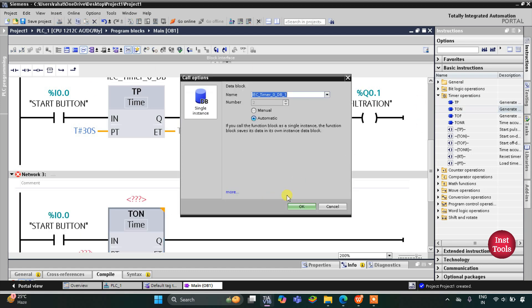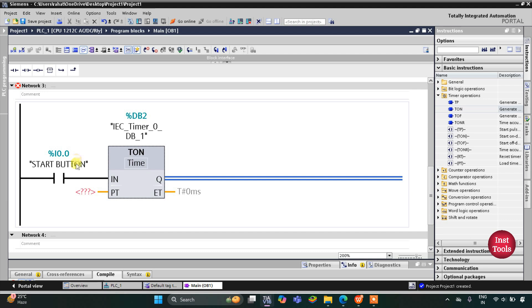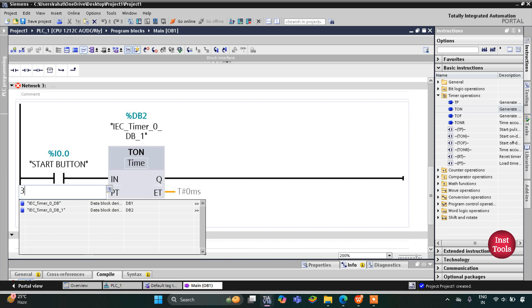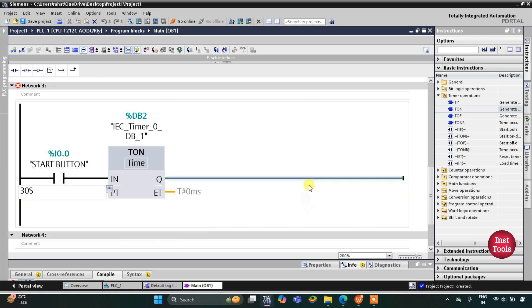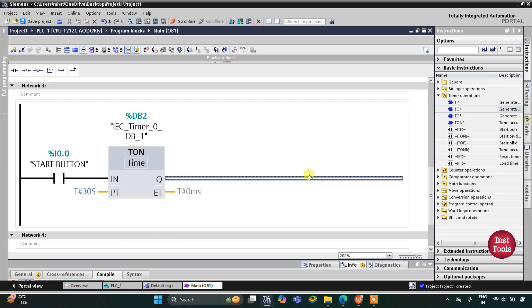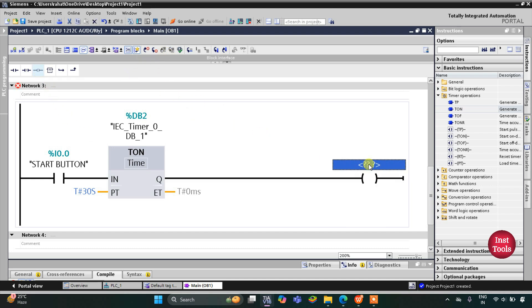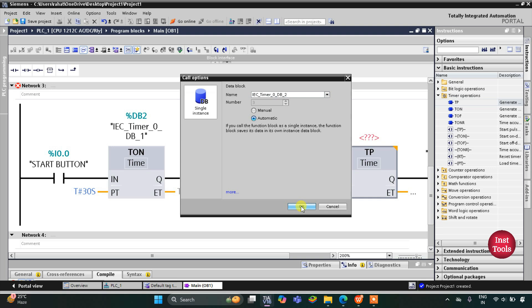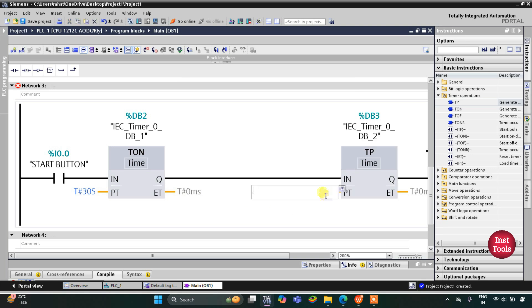After that, when the start button is turned on, after 30 seconds there will be an on-delay timer of 30 seconds, and after those 30 seconds the addition of chemicals will start. For that I will insert a coil for chemical addition, and this process should go on for 5 seconds, so I will insert a TP timer with a preset value of 5 seconds.